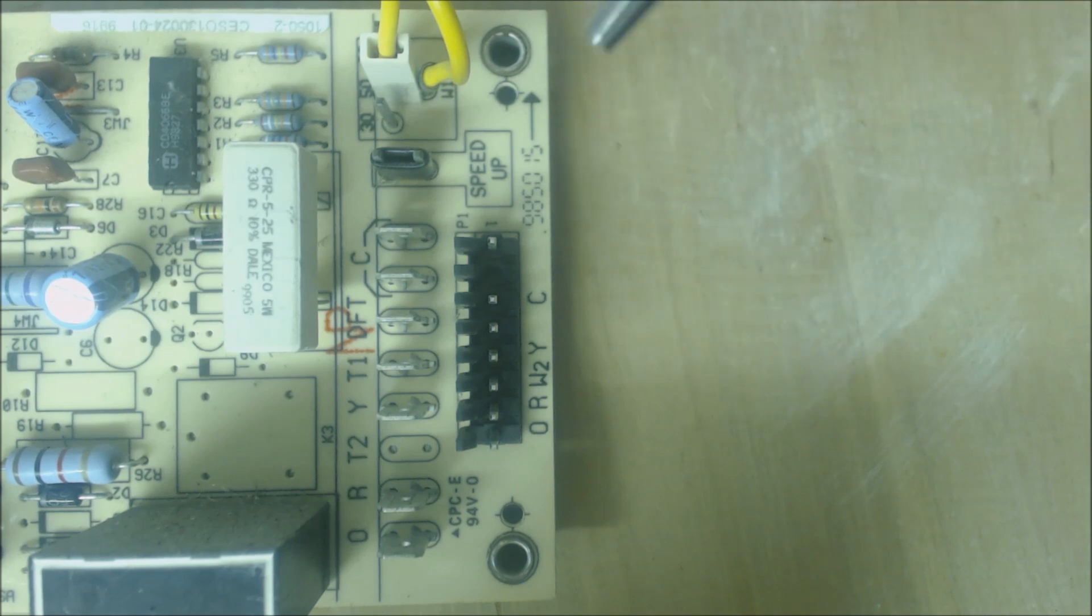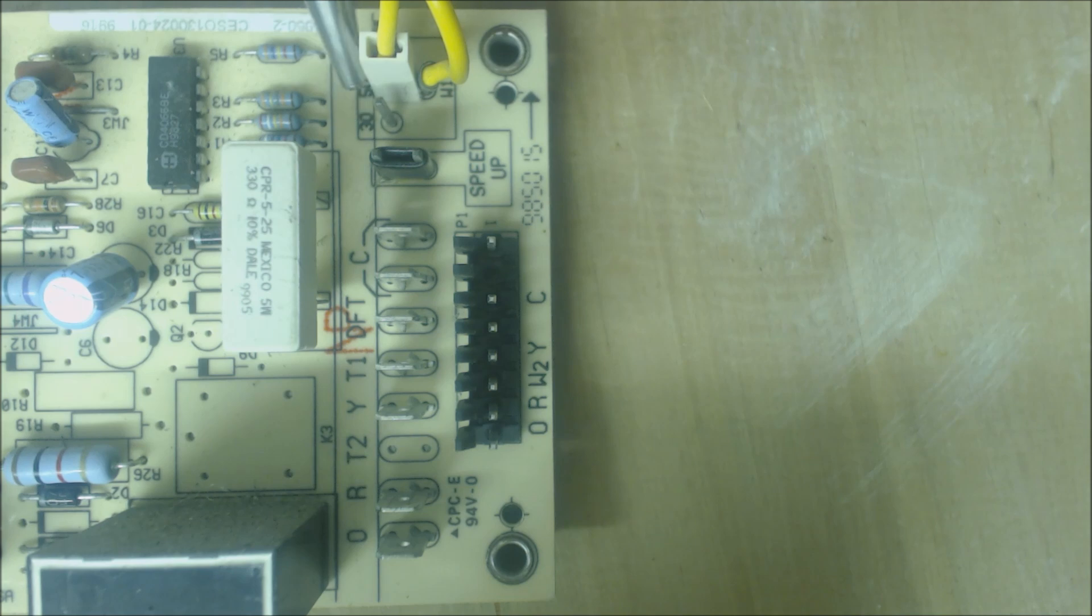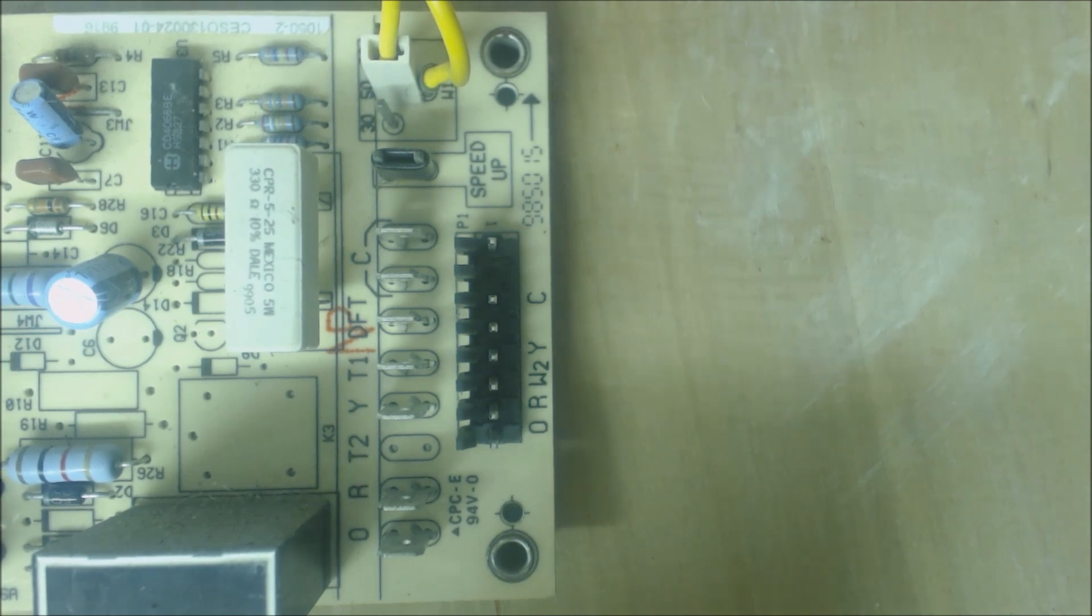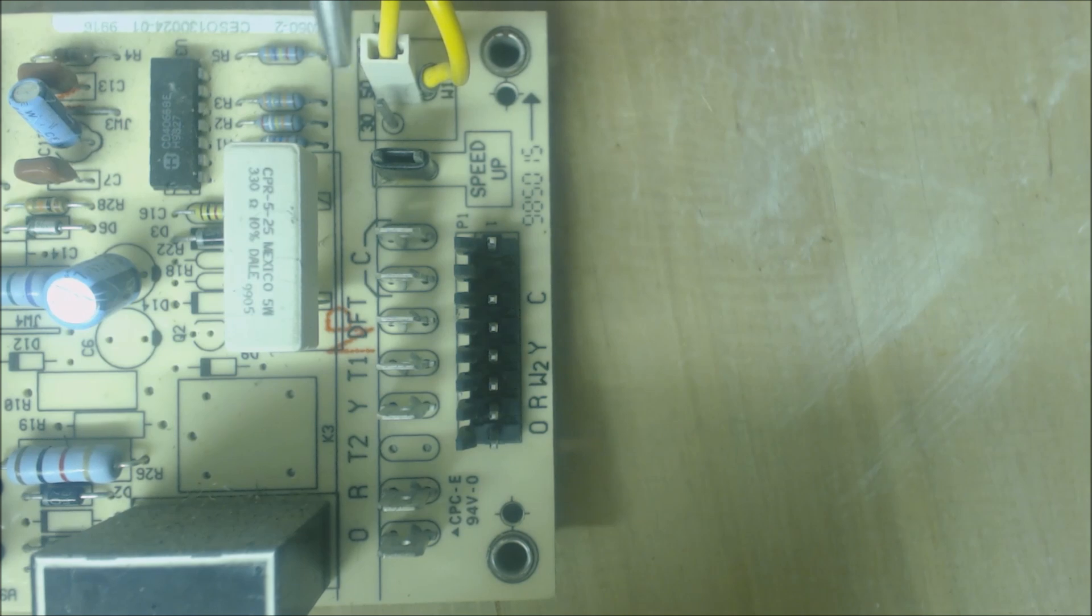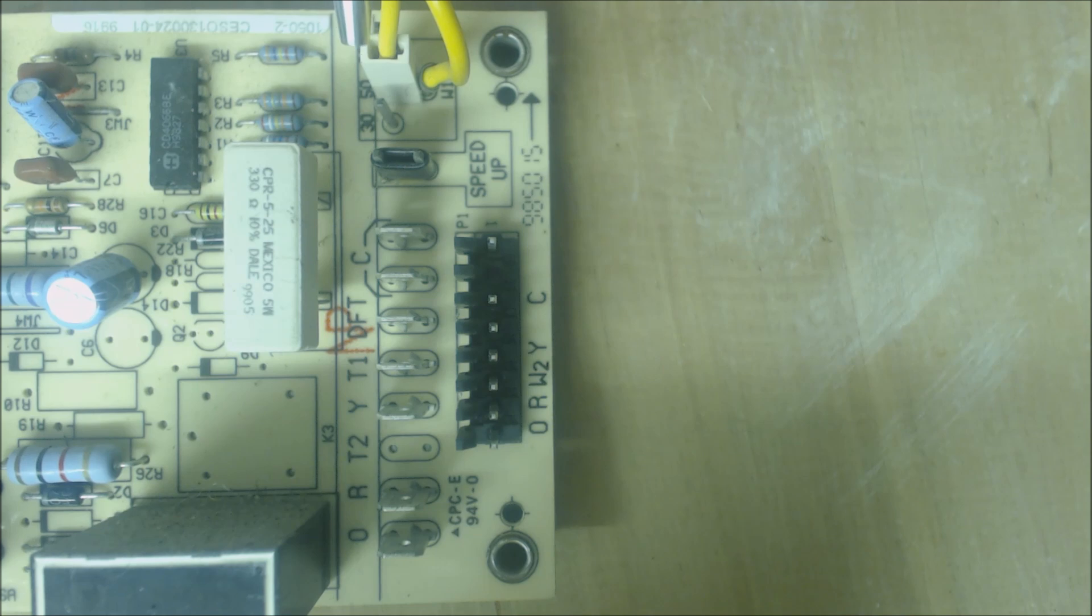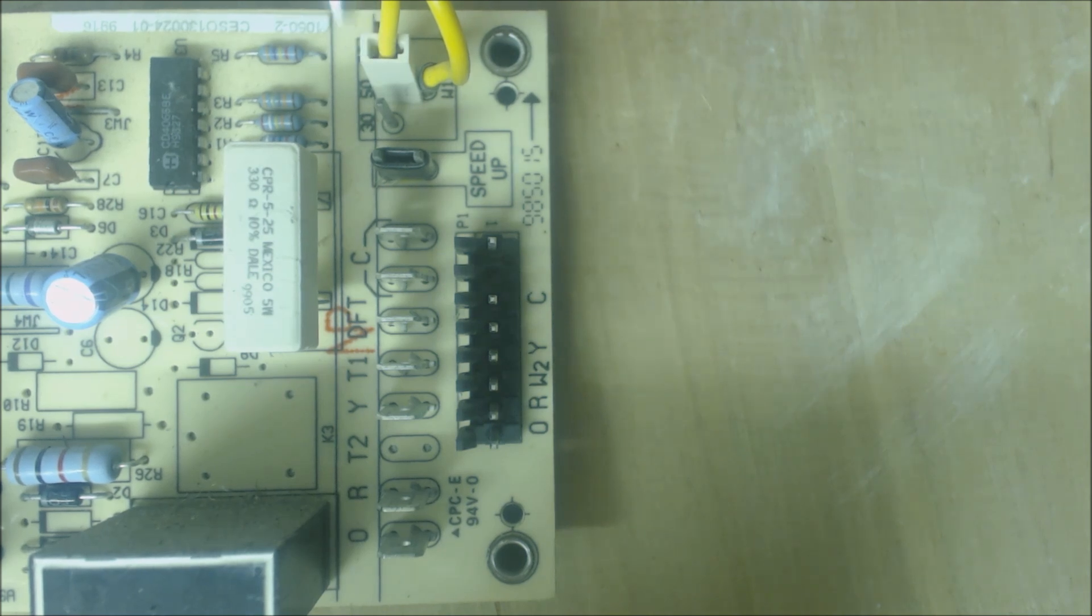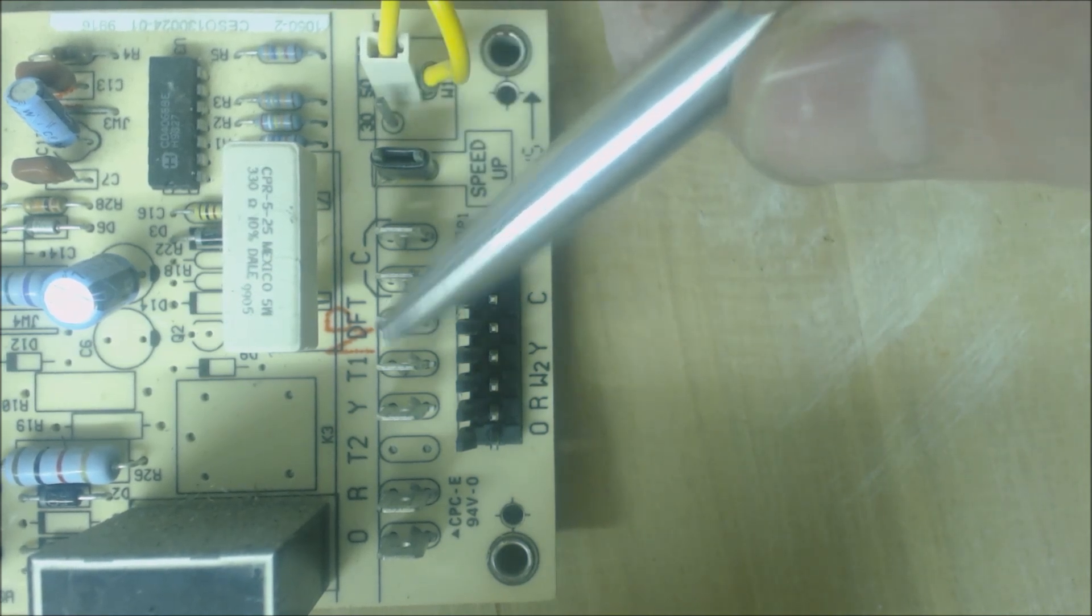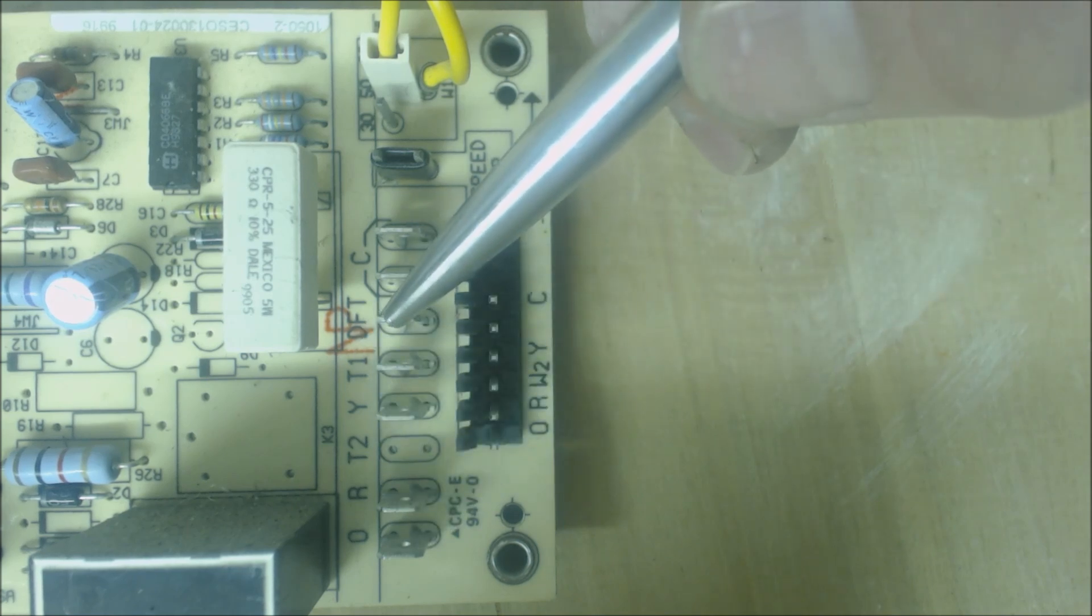Up here you have a settable timer for defrost. You have 30, 50, or 90 minutes. You can select any of those times, and that's a cumulative run time. That means the heat pump could turn on and shut off five times for 10 minutes each time, and that would meet the time requirement of 50 minutes. In order for this unit to go into defrost, you have to have met the time requirement and the DFT to R needs to be closed.